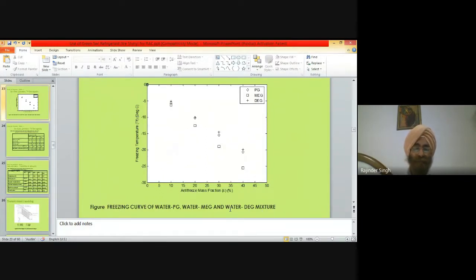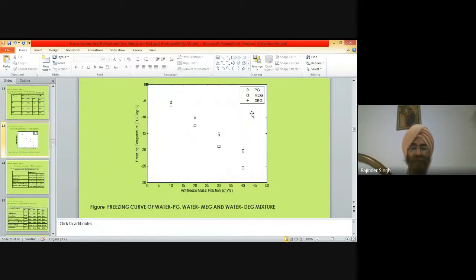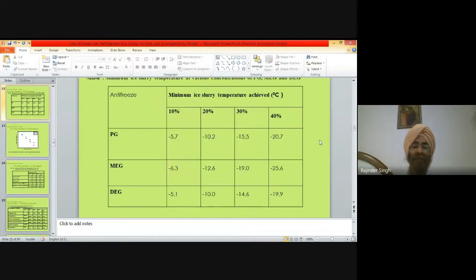This graph shows good results, the freezing curve. On the x-axis is antifreeze mass fraction, and on the y-axis is freezing temperature. As the ice slurry mass fraction increases through 10%, 20%, 30%, 40%, as seen in the result table, the graph shows the same trend: as mass fraction increases, temperature reduces. We have minimum temperatures here for PG, MEG, and DEG. This is the graphical representation of that table.